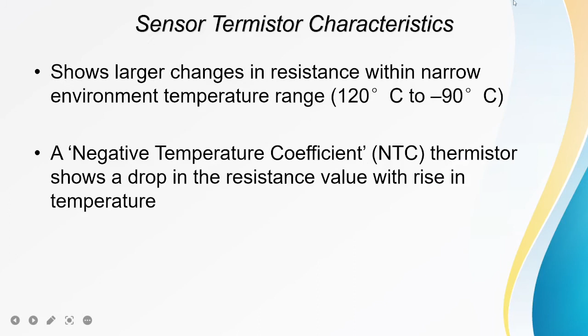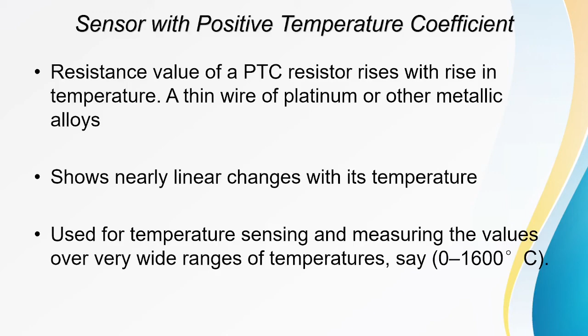So the sensor's resistance value will follow the positive temperature coefficient. Resistance is going to rise with the rise in the temperature. As soon as there is a rise in the temperature, your PTC resistance will also increase. It uses a thin wire of platinum or other metallic alloys, and it shows nearly linear changes with the temperature, so there are not many changes. Then it can be used for temperature sensing and measuring devices over a very wide range, 0 to 1600 degrees centigrade.